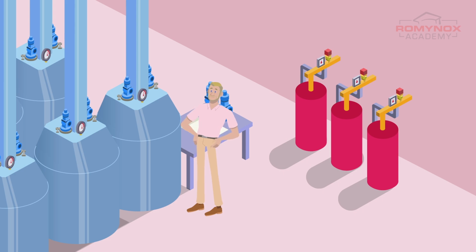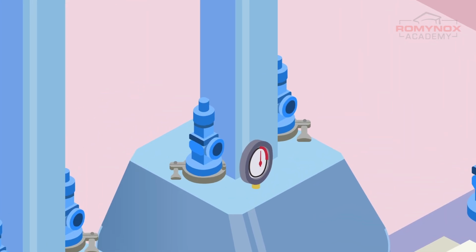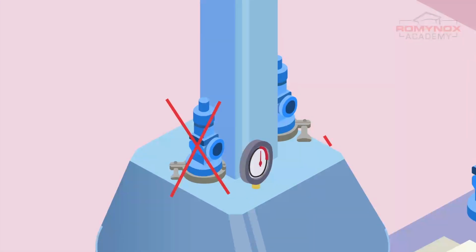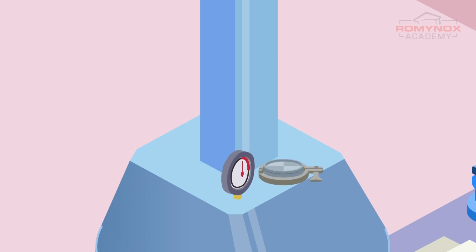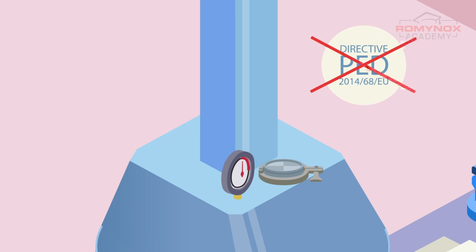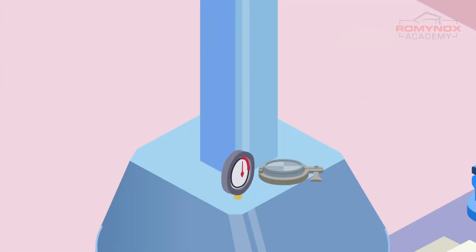Closed systems at less than 0.5 bar positive pressure also need to be made safe. Spring-loaded devices are unsuitable for this purpose. For systems like these, we offer special bursting discs that will always trip below 0.5 bar. This frees the system from the restrictions of the PED and their associated high cost, while ensuring that the process remains safe and 100% closed.